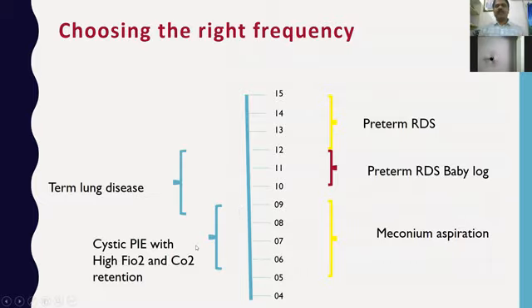And if you have a baby with air leak, cystic PIE, requiring high FiO2, and CO2 retention is there, here you need to remove the CO2. So you need to keep a lesser frequency. You may need to go down as low as even 6 or 5.